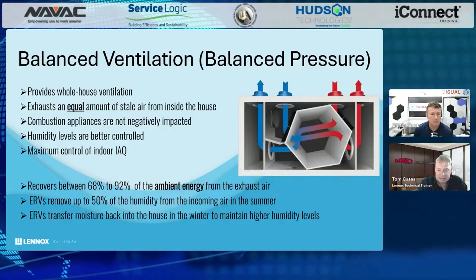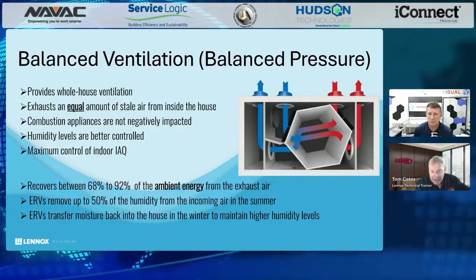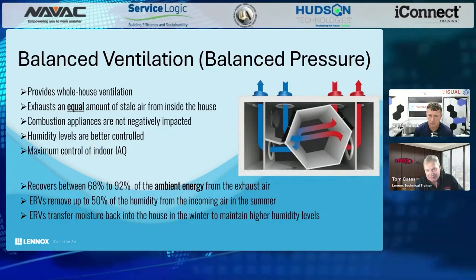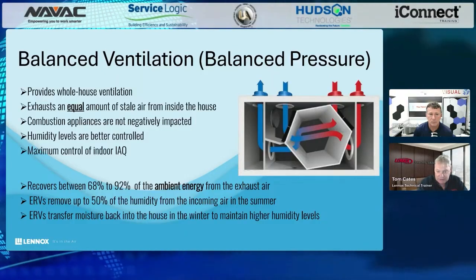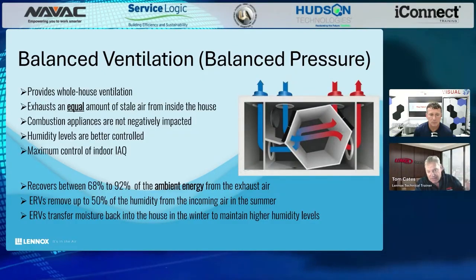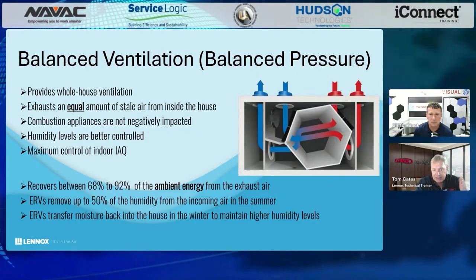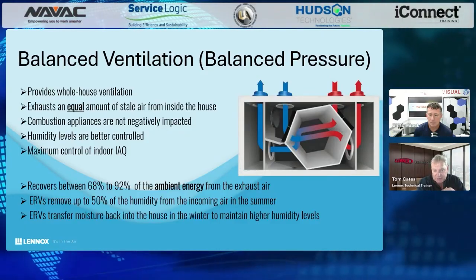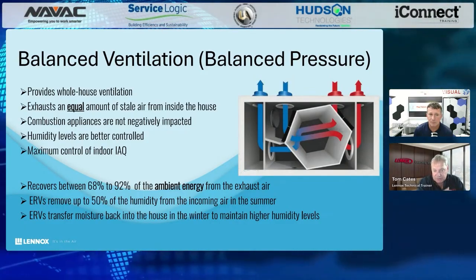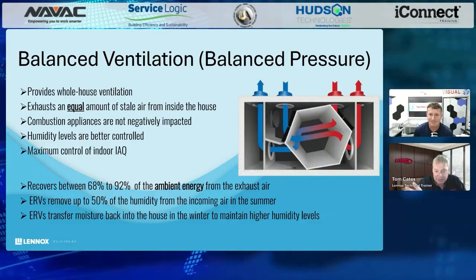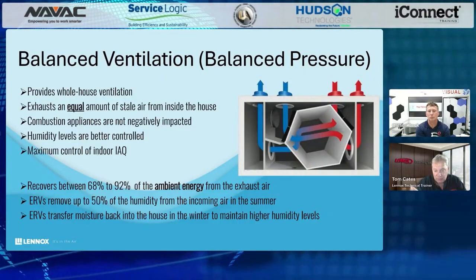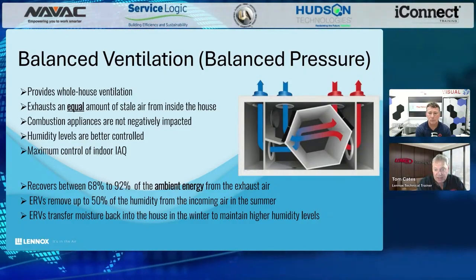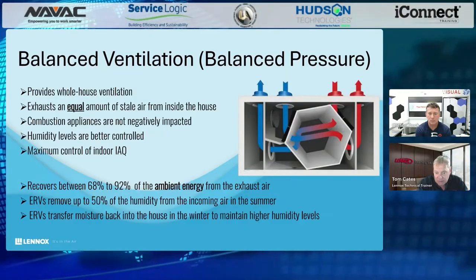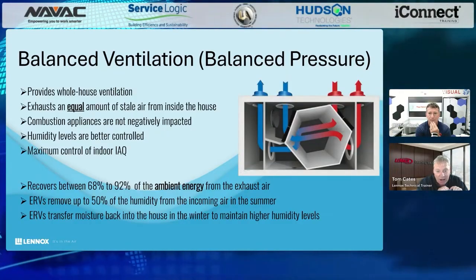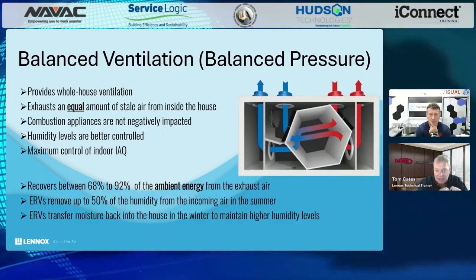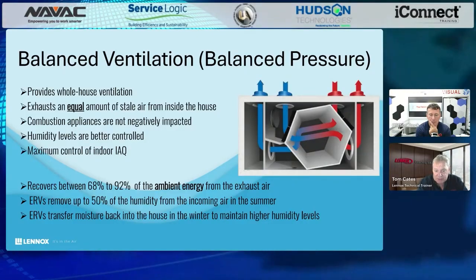And I can save 2/3 of that through the hot air that I'm pushing out of the building at the same time. So I bring in this 32-degree air, and at the same time I exhaust 72-degree air, and I get 60% transfer of heat energy from across the two air streams. I took my 3,000 BTU load that the furnace would have had to deal with, and I reduced that down to 1,000 BTUs of load. And that didn't cost me a dime, Clifton. That transfer of energy is 100% free.